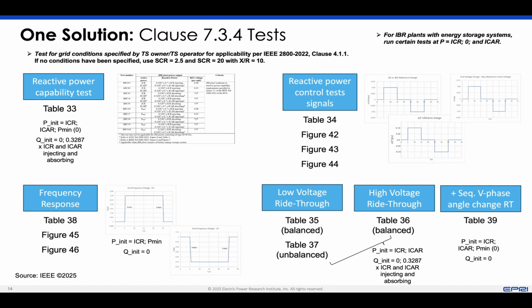Usually that will be the maximum power output or the interconnection continuous rating, and then also the minimum rating. For example, for a wind plant, that might be around 15 or 20%. But in those cases where the IBR plant has storage, then these tests shall also be run at the maximum active power absorption of that storage element from the grid, and that's called ICAR, interconnection continuous absorption rating, as well as around a zero operating point. Because the idea is to really test whether all the controls and the sign conventions and everything has been implemented adequately. So let's actually look at some of those tests.